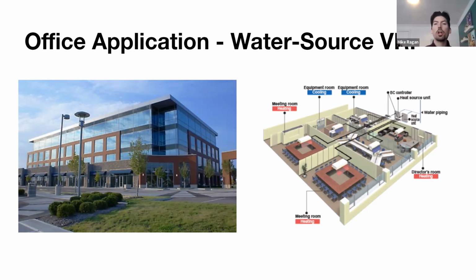But for this, we're talking about water source equipment, where we're not absorbing or rejecting heat from the outside air. Instead, we're going to be absorbing and rejecting it from a water loop. So in this instance, we have two different water source heat pump systems. One of them is serving the left side of this building, the other is serving the right side.